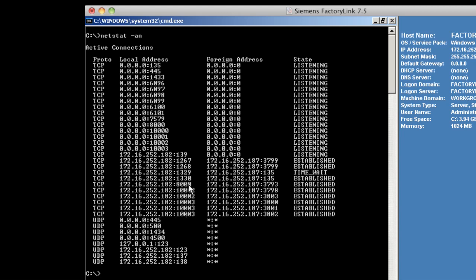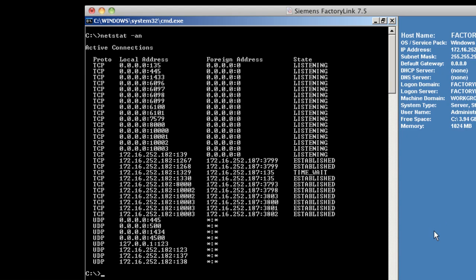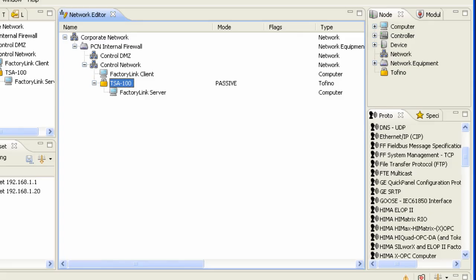8,000 is actually used by factory link for the licensing component. And then we also see some 135, which is used by classic OPC as the RPC endpoint mapper, which is used to actually determine this number in the initial communication. And then we see a couple other ports and services that are being used here. It looks like a couple services are accessing the client here on 3799.